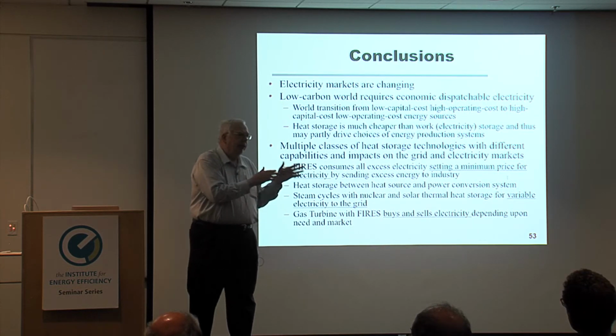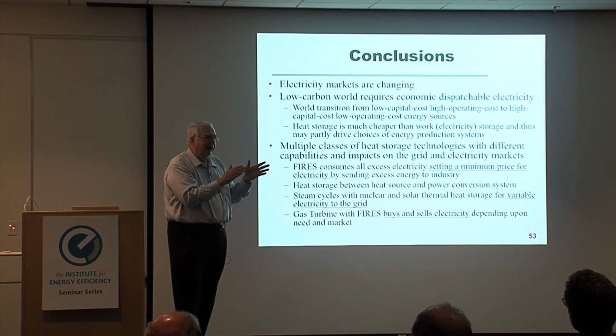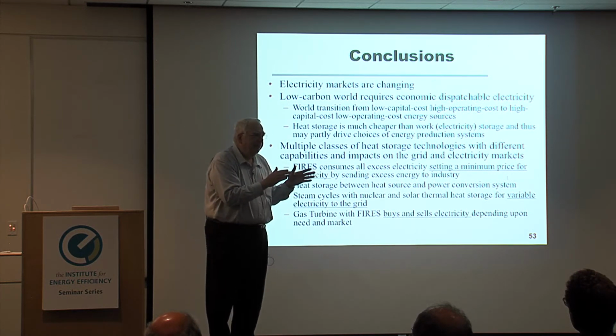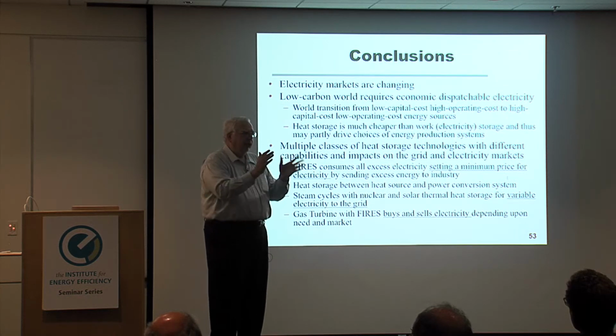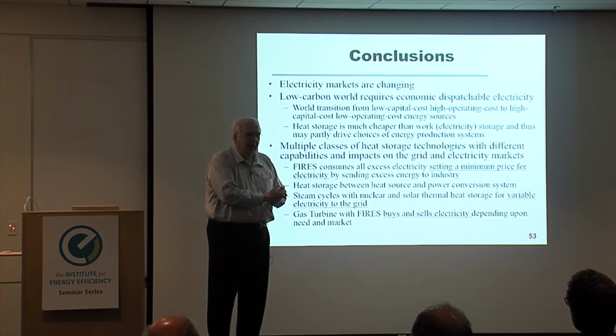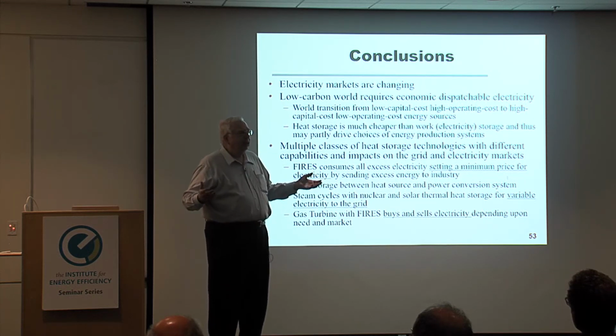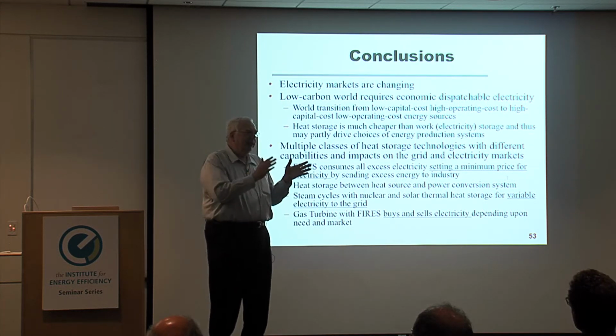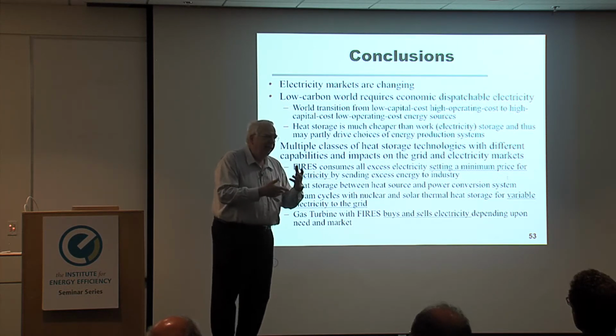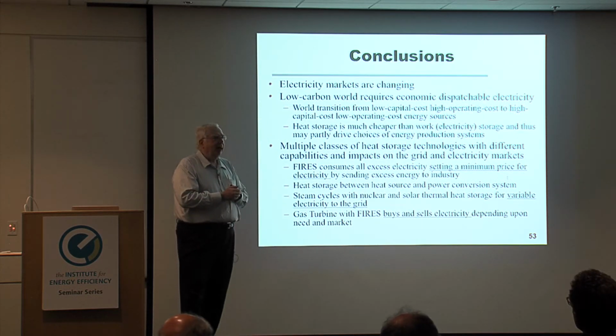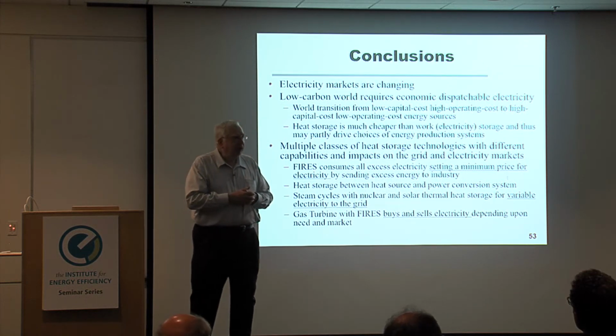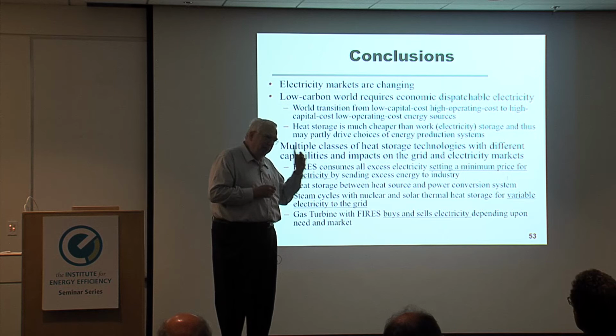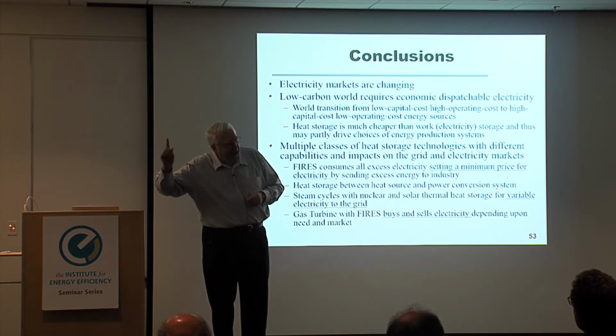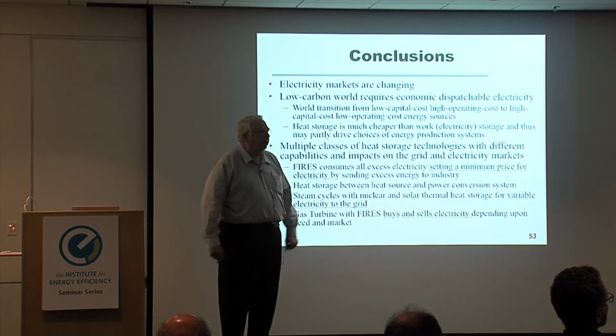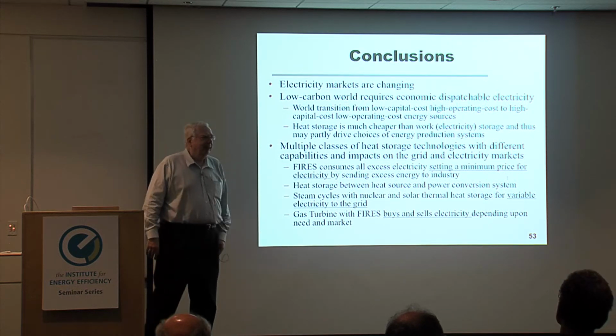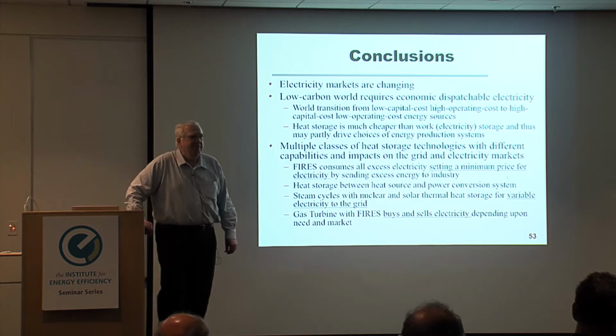So when we're running FIRES, discharging them, we're cooling the outer layer of insulation. When we go into charging mode, the inner insulation layer and the outer insulation layer are just cold. So it essentially acts as a heat absorber as well as an insulator. We have this strange dynamic insulation system where our heat losses can be very, very close to zero, because the input is cold air and the output is hot air. That's because that's what couples to everything. It's a very unique system, and otherwise you'd normally worry about these things.